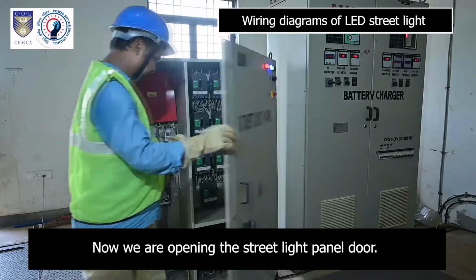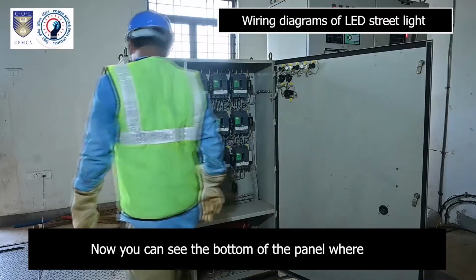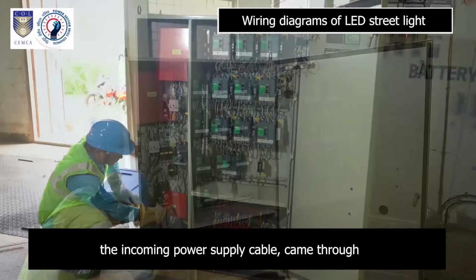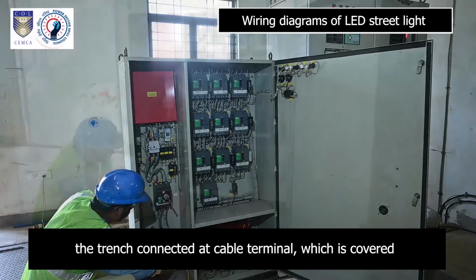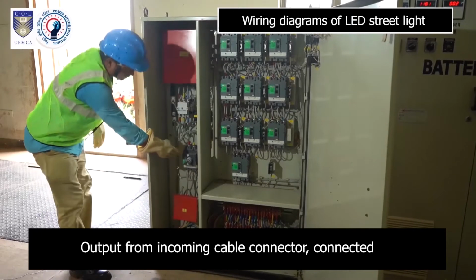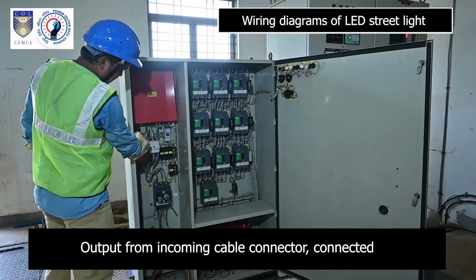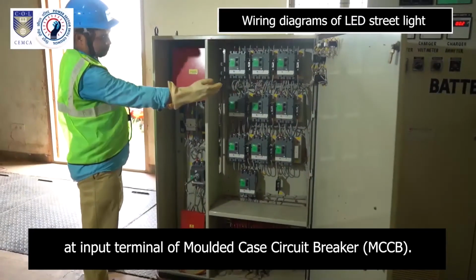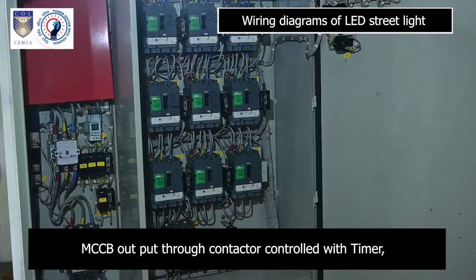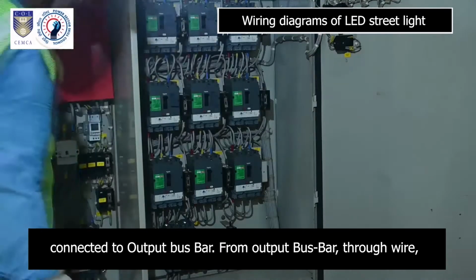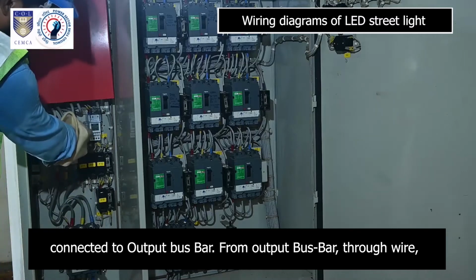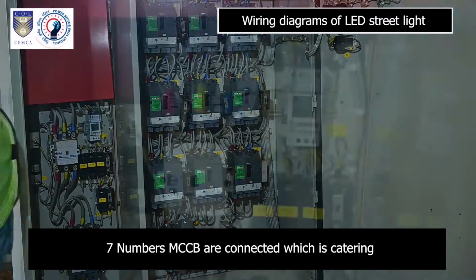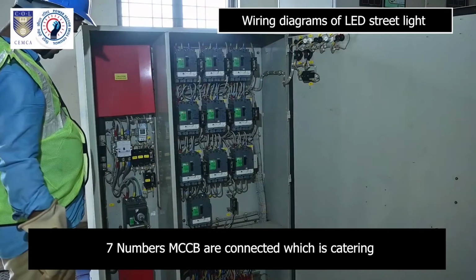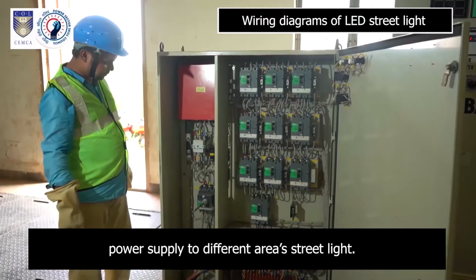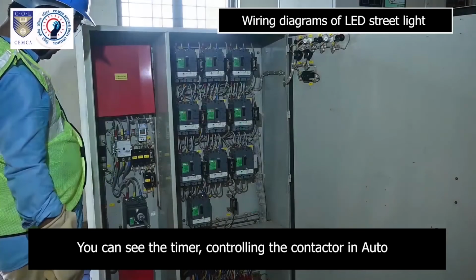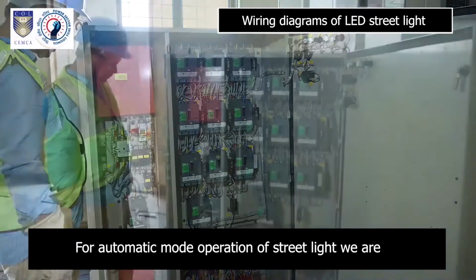Now we are opening the street light panel door. Now you can see the bottom of the panel where the incoming power supply cable came through the trench connected at cable terminal, which is covered with insulation sheet for protection purpose. Output from incoming cable connector is connected at input terminal of molded case circuit breaker MCCB. MCCB output through contactor controlled with timer is connected to output bus bar. From output bus bar through wire, 7 numbers of MCCB are connected, which is catering power supply to different areas street light. You can see the timer controlling the contactor in auto mode for switching on and off the street light.